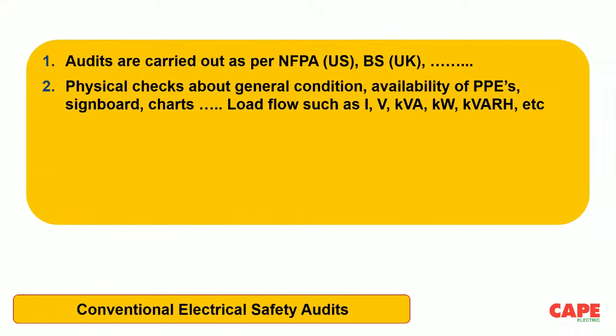Mostly the auditors, I don't use the word verification here because conventionally we are only doing audit. We don't have the habit of making verification. Conventionally, the auditors are doing some kind of physical check. They walk around the installation, find out whether there are any hanging cables, dust on the panel boards and so on. Then they check the general condition, availability of PPEs, signboards, circuit charts, tables, and so on. Plus, in some cases, load flow analysis is also made, like the used power, the reactive power, and so on. But please note that load flow analysis is not a safety subject; it is something else.